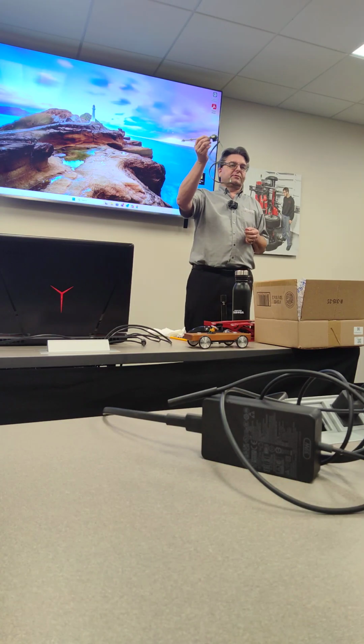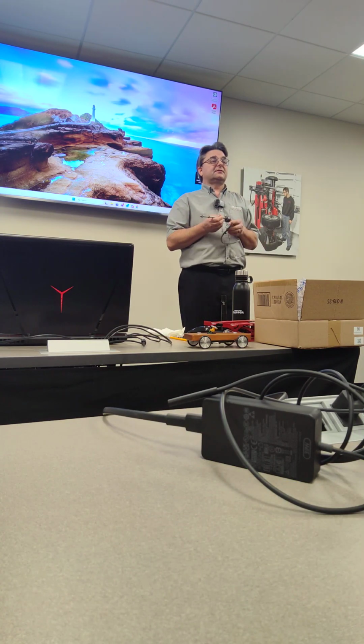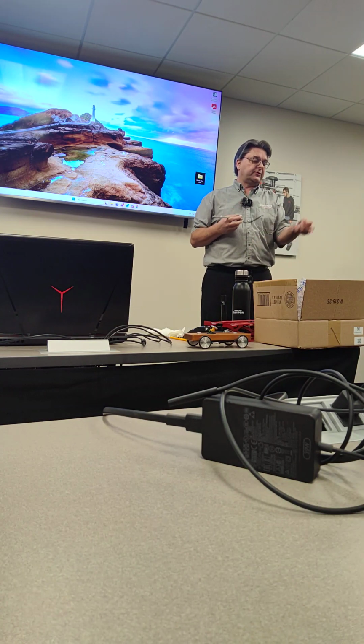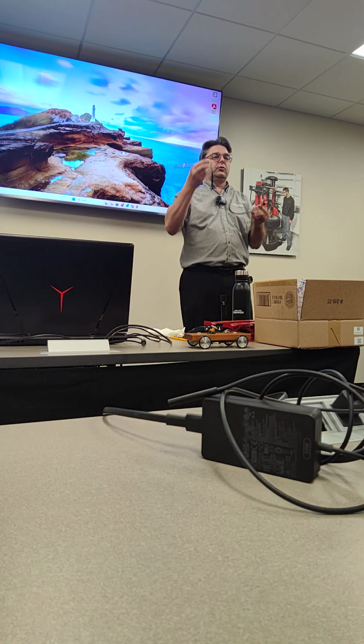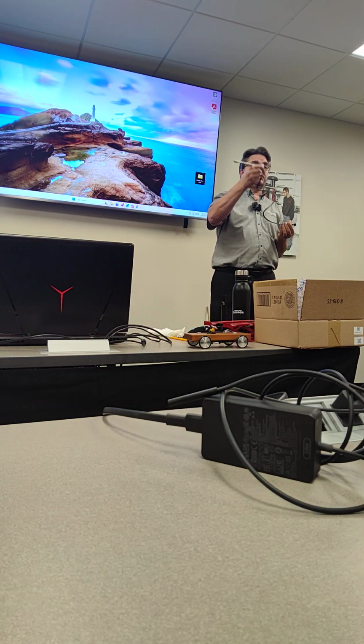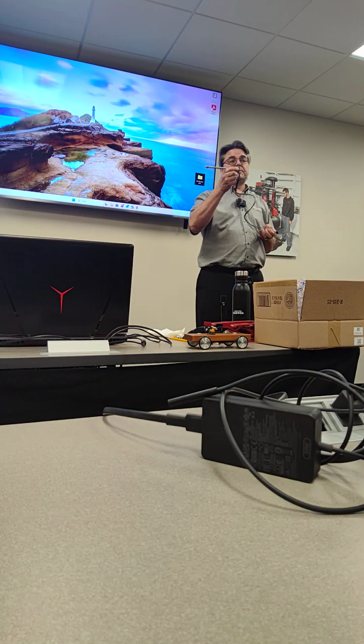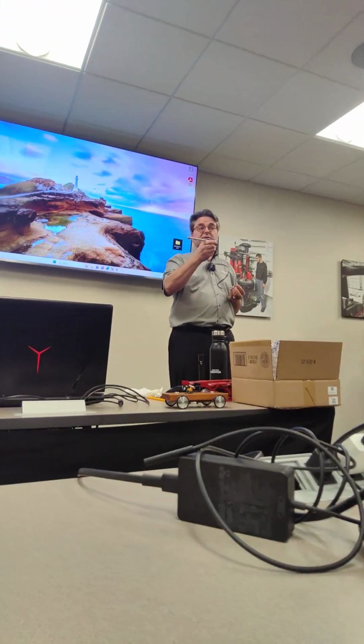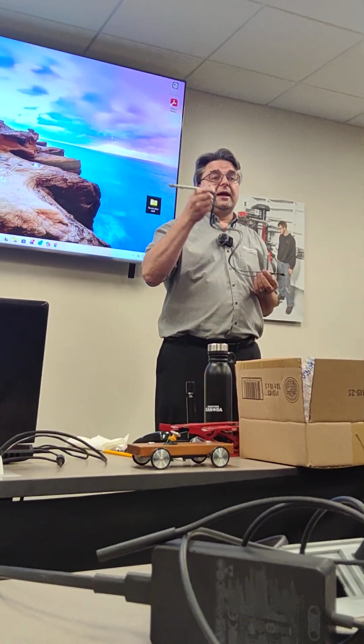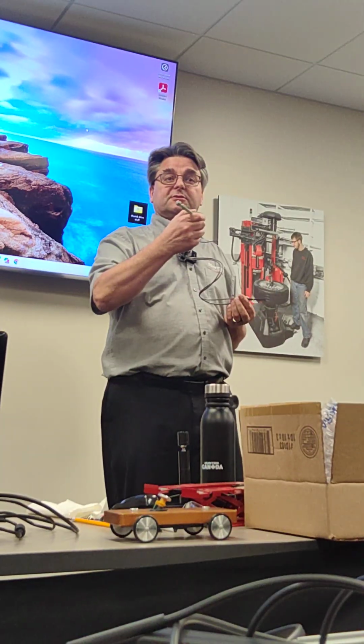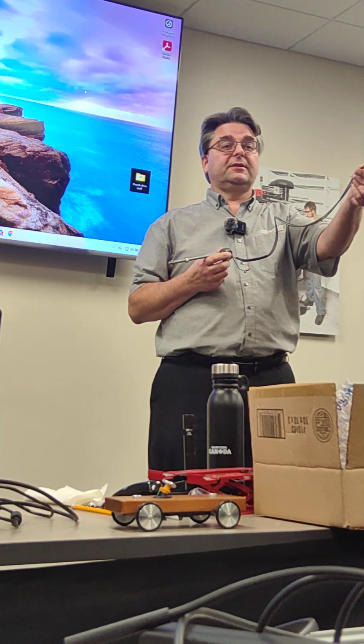Force transducers, you have to put these in, and this is another thing: you always want to have the shorting bar on here when you either replace or adjust. A lot of times people will go in and check the adjustment on the force transducers, and while they do that, the balancer's off.